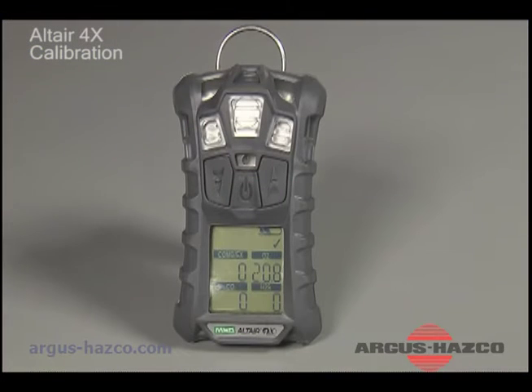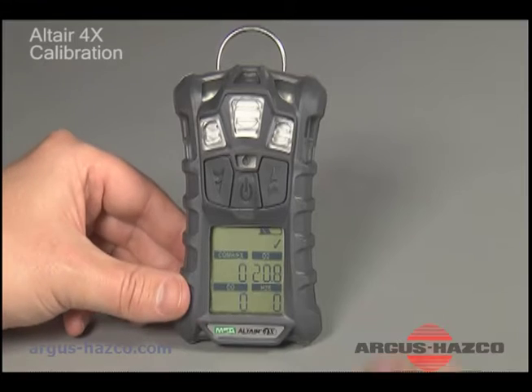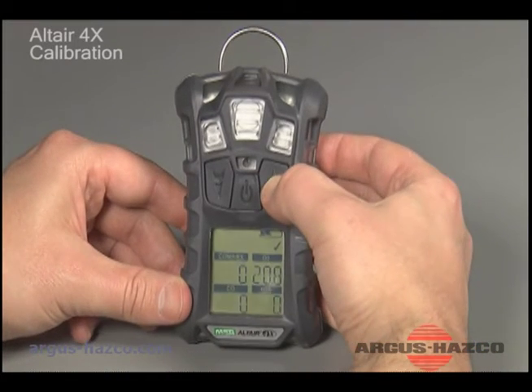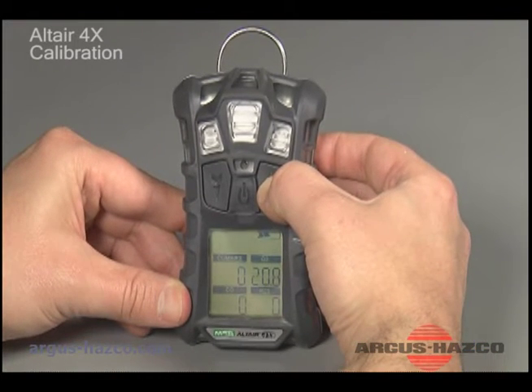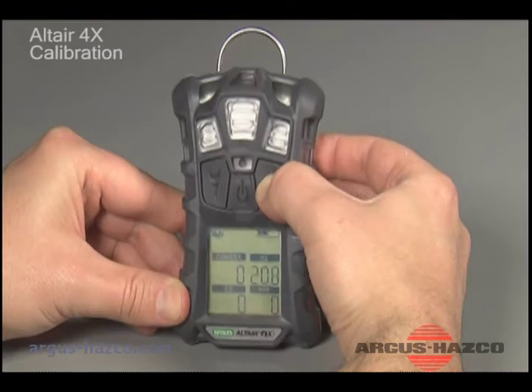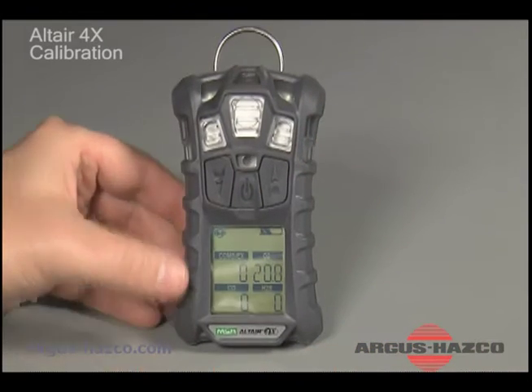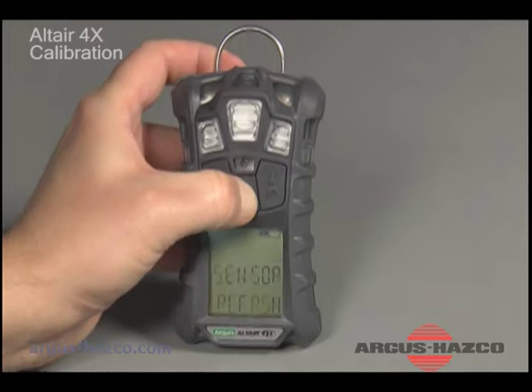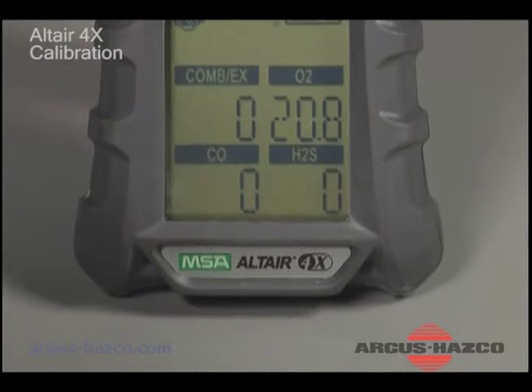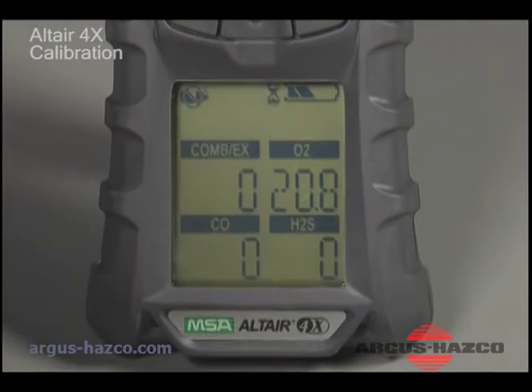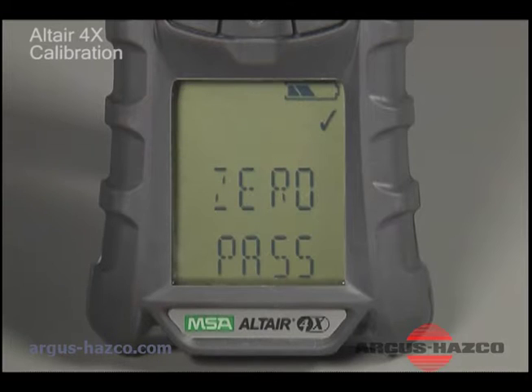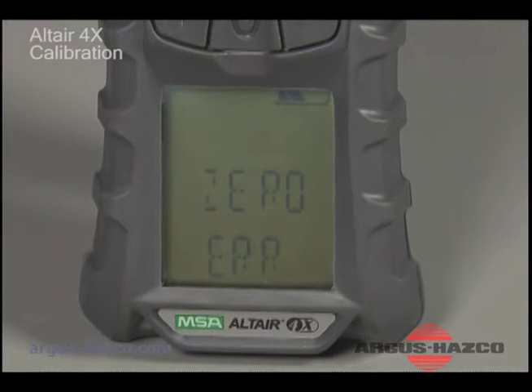To perform manual calibration, when in measure mode, press the Page Up button for 3 seconds until 0 cal displays on screen. Next, press the Accept button to begin calibration. First, a sensor refresh will automatically perform, followed by 0 calibration. If 0 calibration is successful, 0 pass will display. If 0 calibration is unsuccessful, 0 error will display.